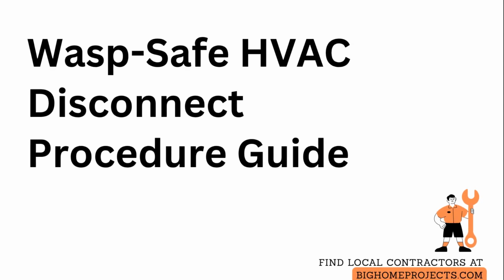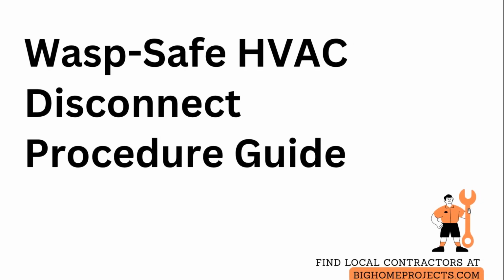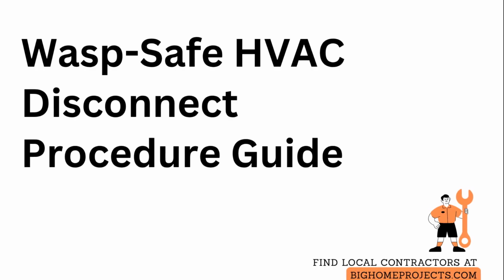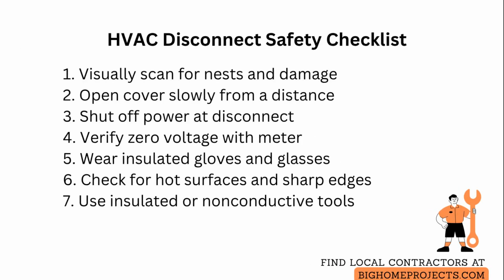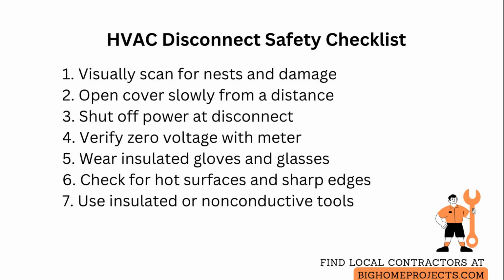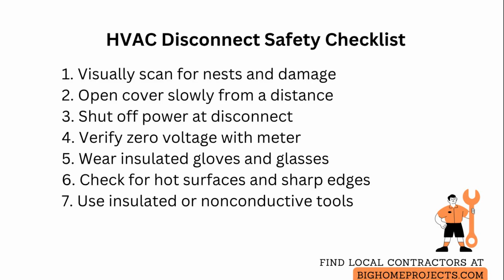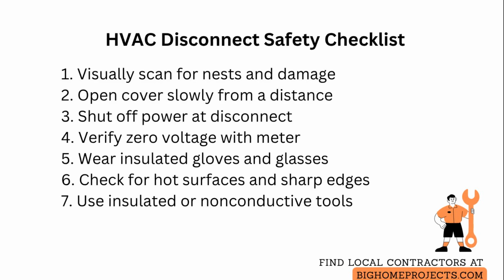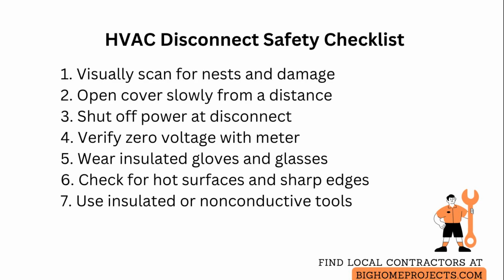Always assume the disconnect or panel could be energized or harbor hazards like aggressive insects before you put your hands on it. When opening a disconnect or panel on an HVAC unit, start by visually scanning the area for insect nests, frayed wires, corrosion, and water intrusion so you know what you might face. Stand back and open the cover slowly using your free hand to steady the panel and your eyes to catch any sudden movements like wasps fleeing a nest.